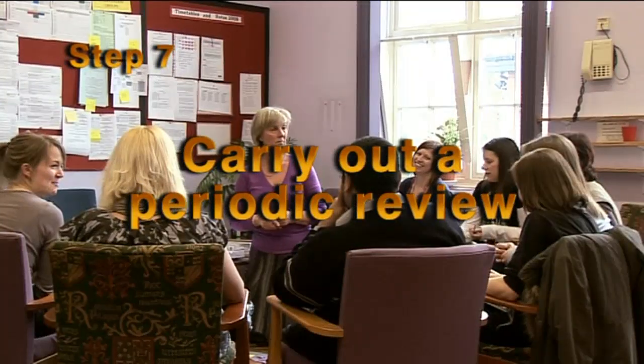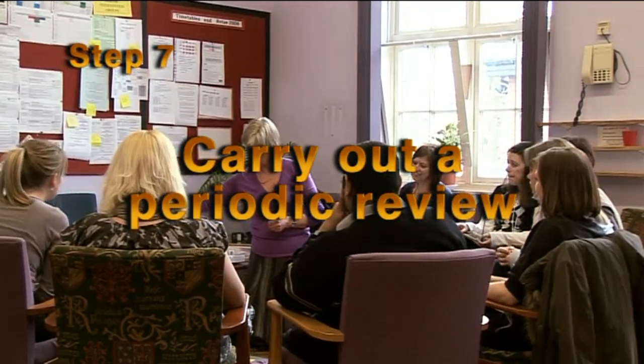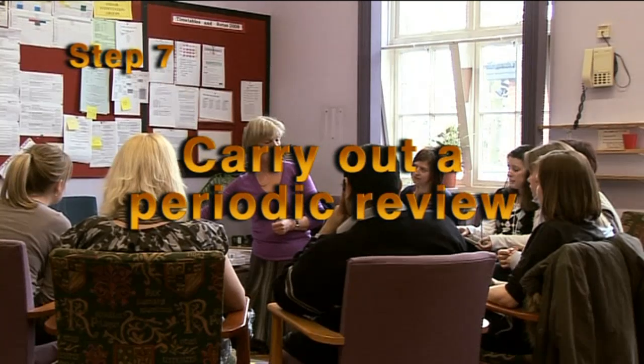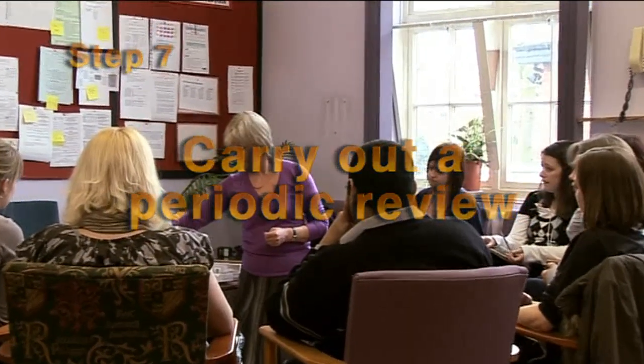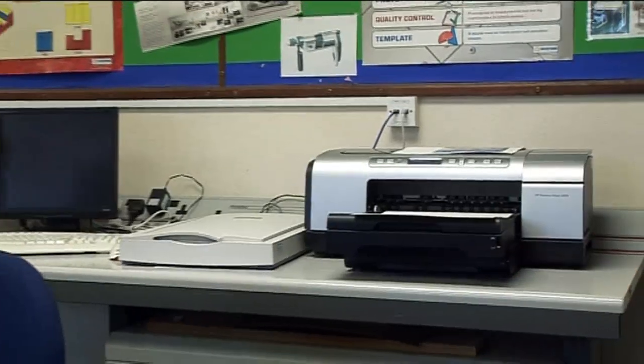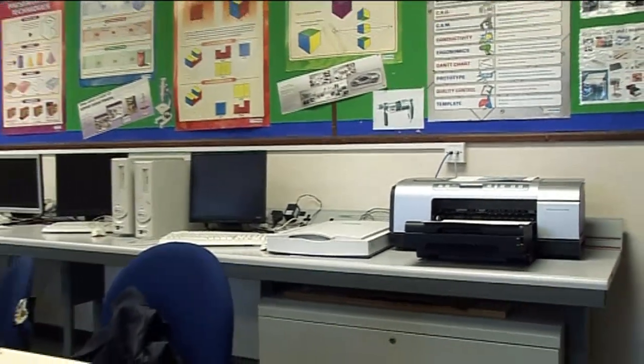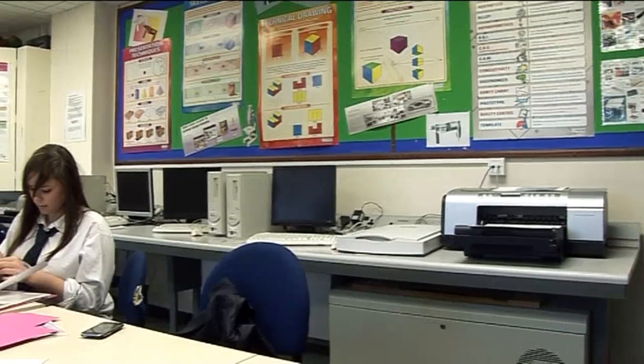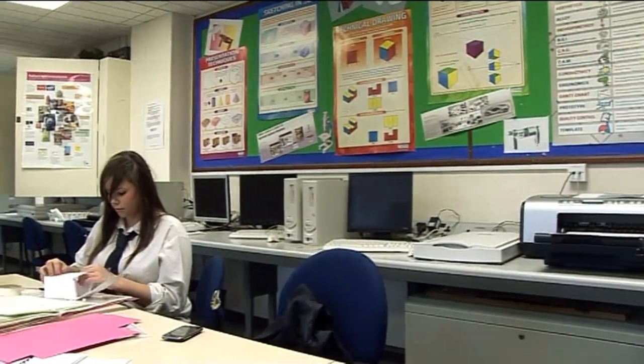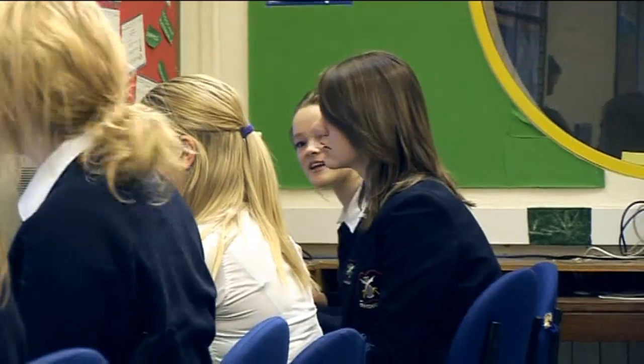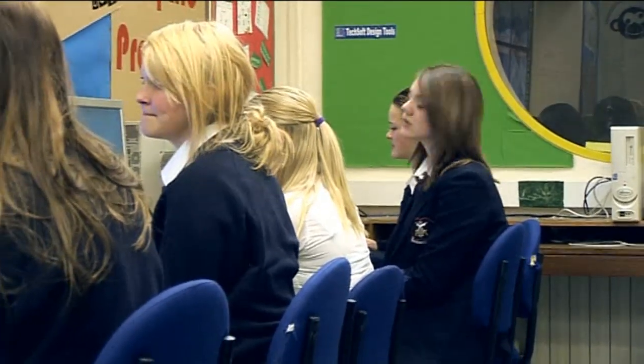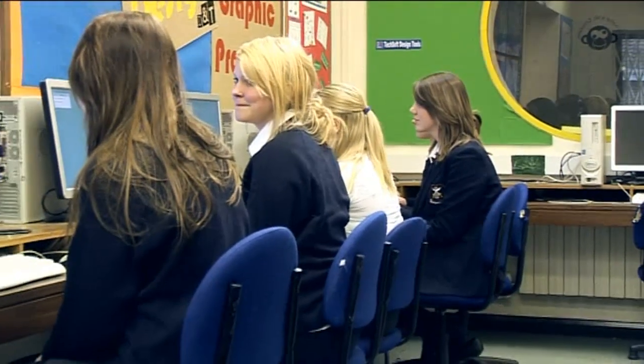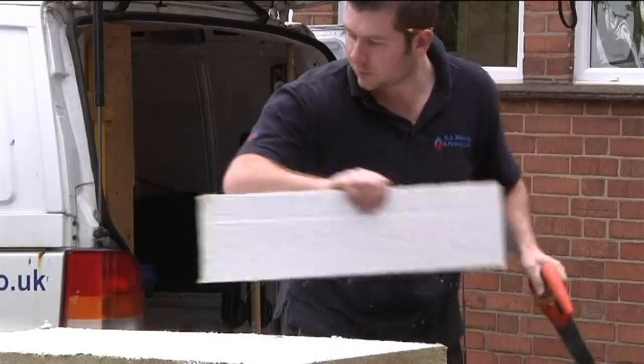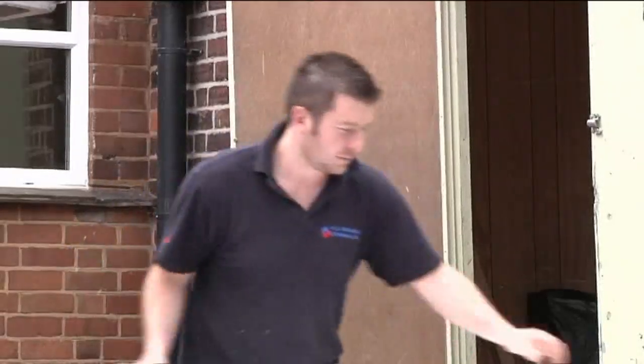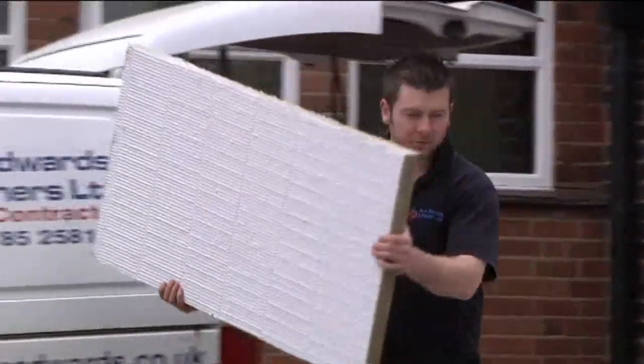The review step is crucial in maintaining fire safety. Every assessment should be reviewed at least annually, if only to confirm there has been no change in circumstances. Where and how often reviews take place may depend on the tasks undertaken and the environment. Obvious changes like the change of use of an area within a school, the introduction of new materials or equipment, building alterations and extensions are automatic triggers for reassessments.